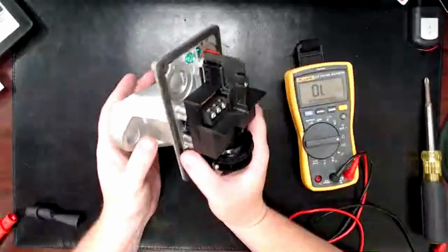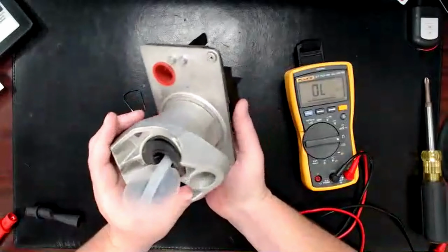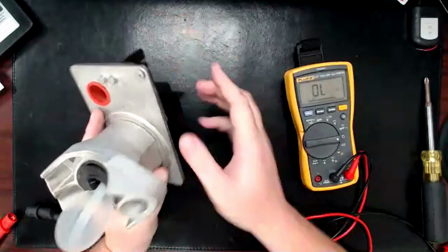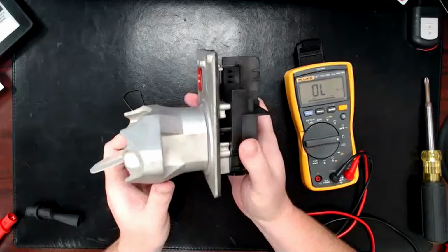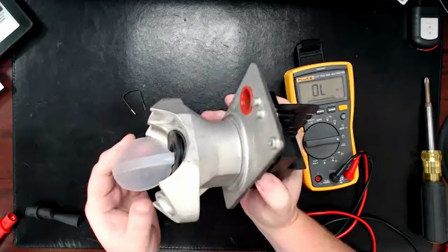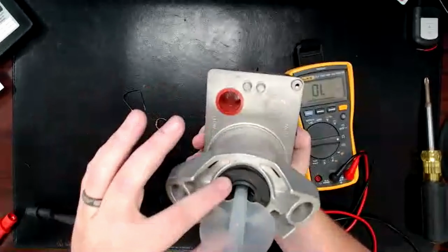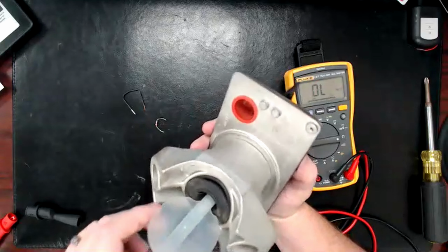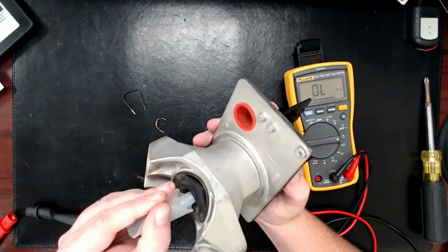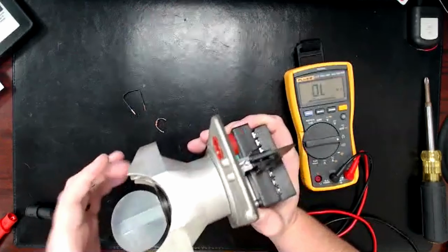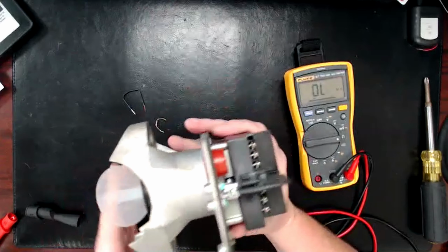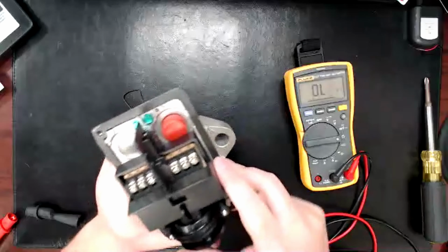So this is the water flow switch. Back here, you can see there's flow indicators. So that's the direction of the water flow. It only works one way. And this is the paddle that the actual water pushes on. This right here is a rubber grommet that seals against the hole. The hole in the pipe is only this size. And so the paddle actually has to fold up to get pushed in there. And then when it sits in the pipe and the water flows against it, it can push it up and down. And then here on the front, this is the part we're more used to working with.